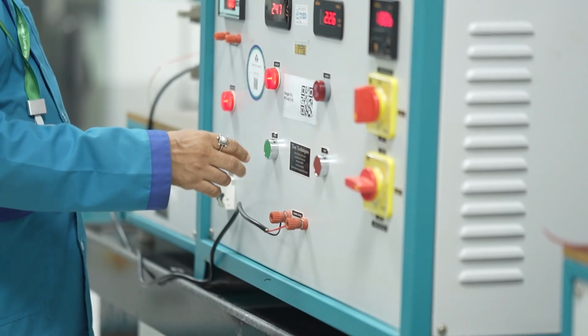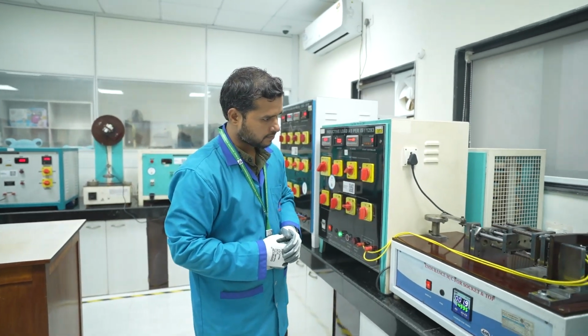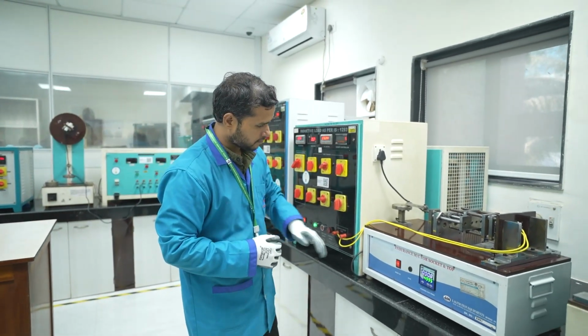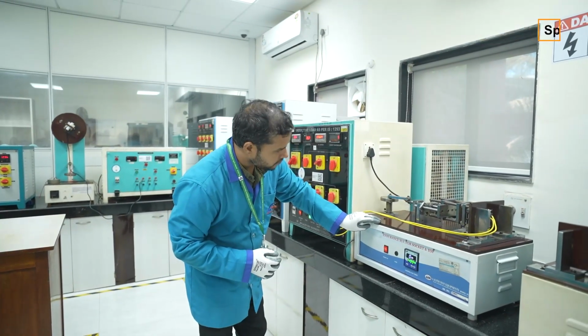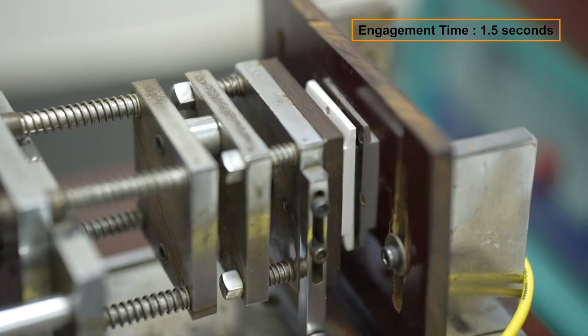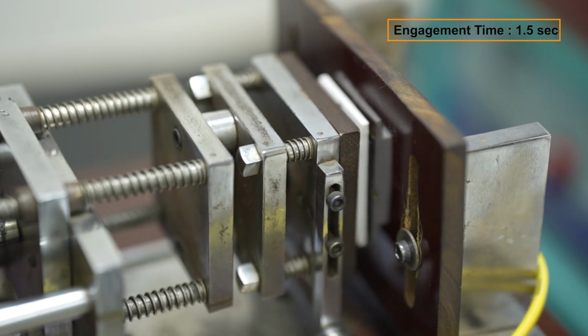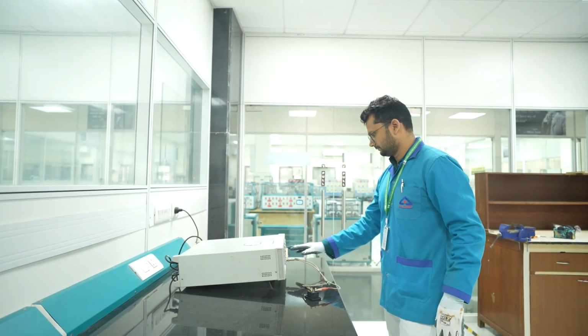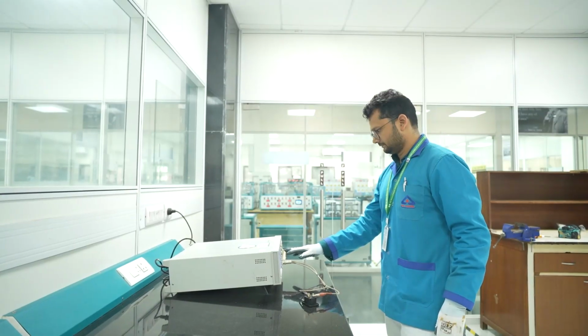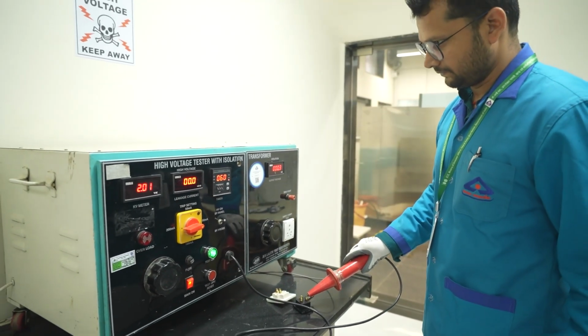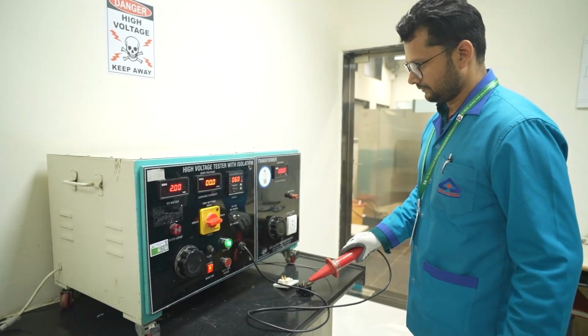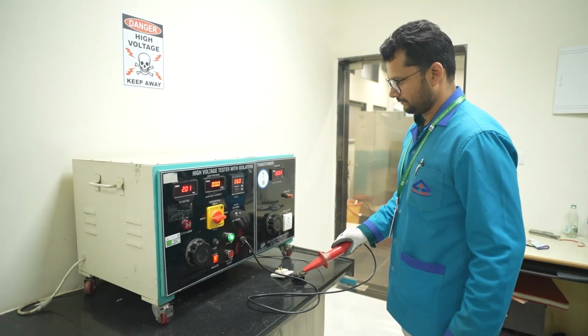Normal operation, clause 21. Accessories undergo 10,000 engagement and disengagement cycles at a speed of 30 strokes per minute with a 1.5 second engagement time. Following this, insulation resistance and high voltage tests are conducted to ensure long-term durability and safety.